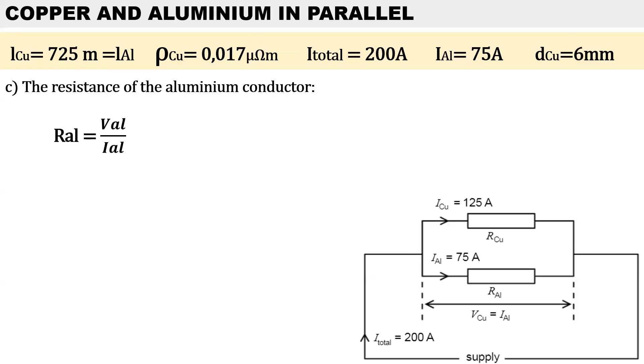To calculate the resistance of the aluminum conductor, we can use Ohm's law. The resistance of aluminum will be the volt drop divided by the current through that branch: 54.5 volts divided by 75 amps, giving 0.727 ohms.